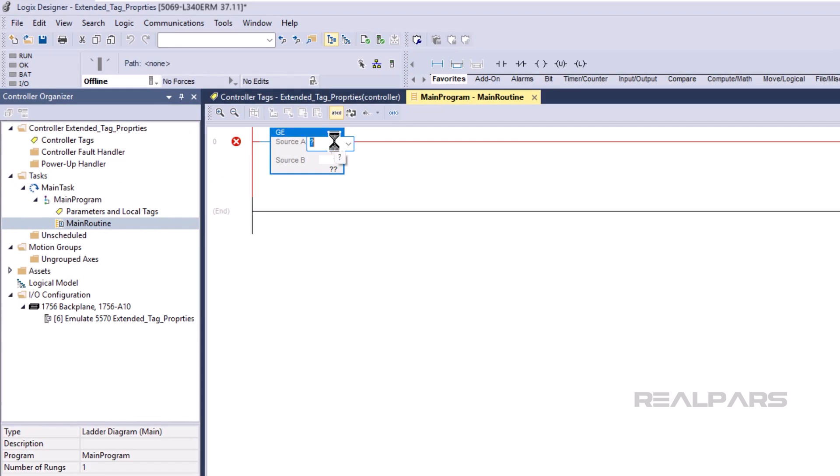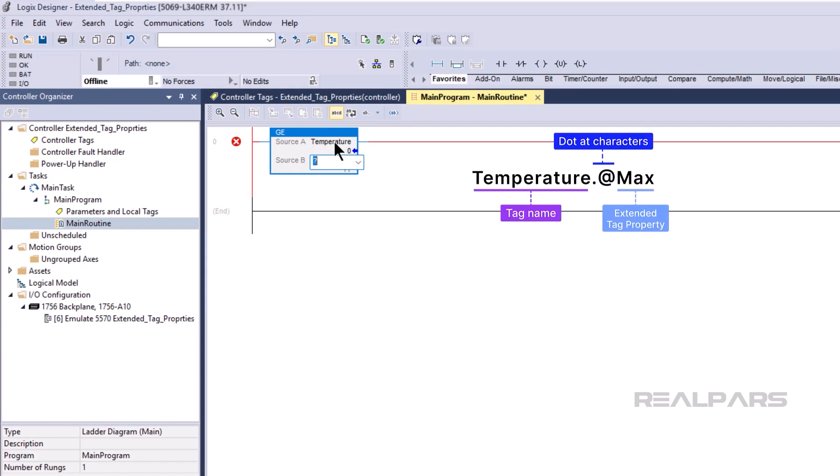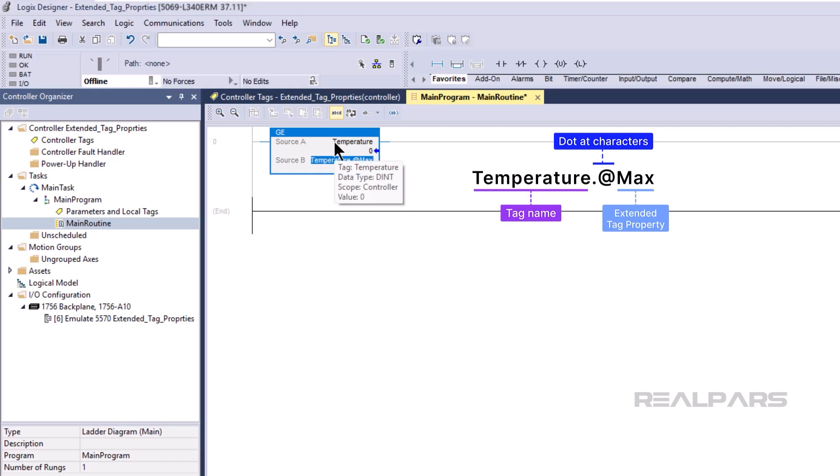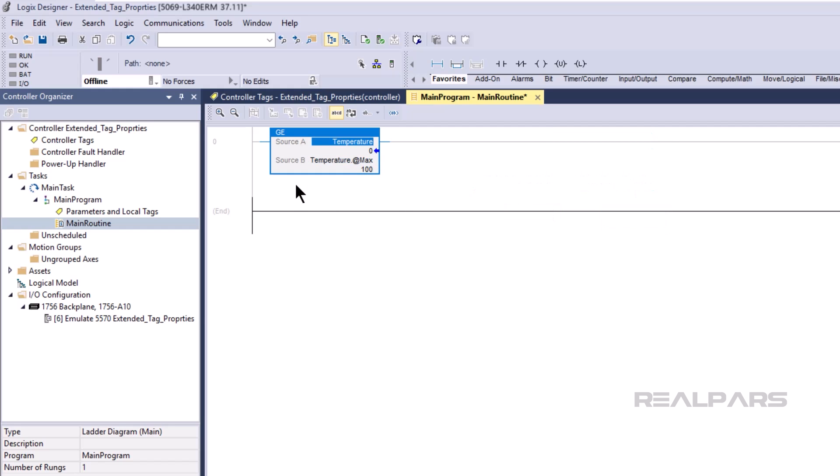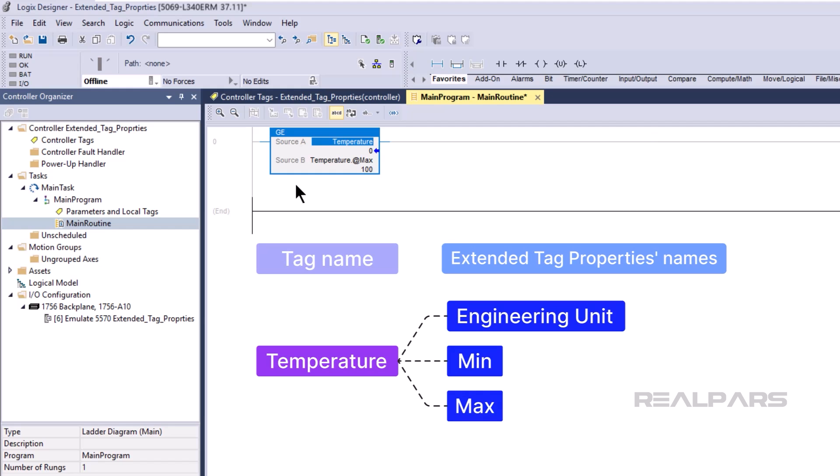To use .@ notation, you can type the name of a tag followed by the .@ characters, followed by the name of the Extended Tag Property that you want to read. To access an Extended Tag Property, you need to know the names of the Extended Tag Properties that have been configured for the tag. Unfortunately, they cannot be found in the tag browser.